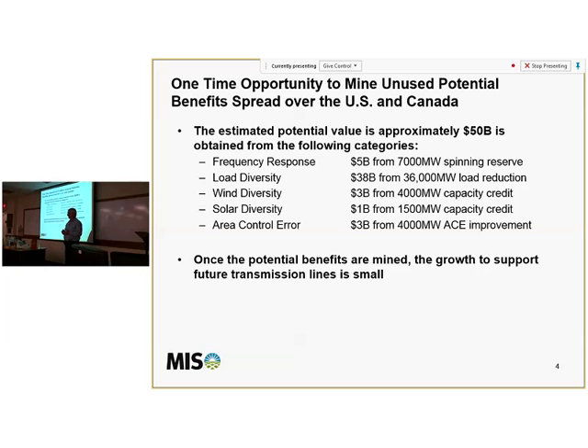When I started with wind in 2002, they told us that the maximum amount of wind you could put on Miso and SPP together was 10,000 megawatts, because we couldn't control the system any more than that. Well, we have 12,600 megawatts in Miso alone, and we're controlling it quite well. One reason is the diversity in the geographic location of those generators. We found out in the EWITS study, the Eastern Wind Integration Transmission Study, that not only do you get up to about 25% capacity credit, but you could reduce the variability of wind by a factor of 3 if you aggregated them with transmission.